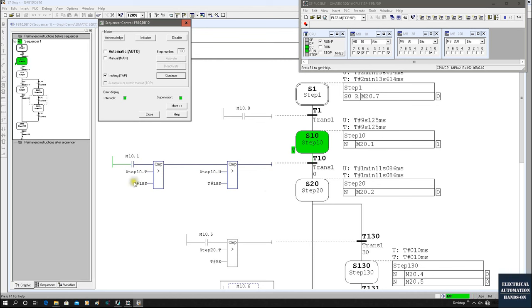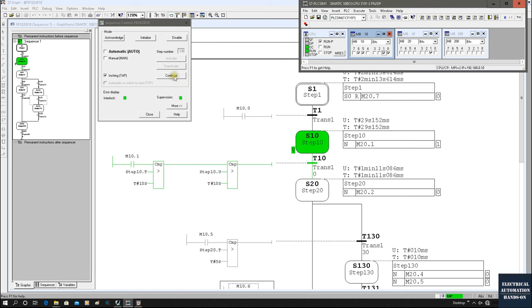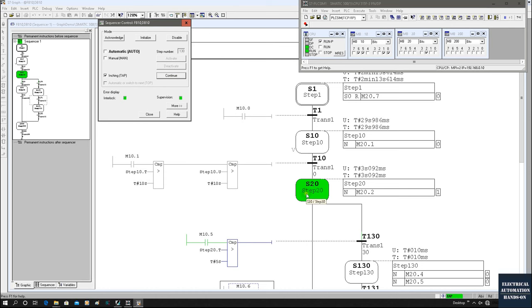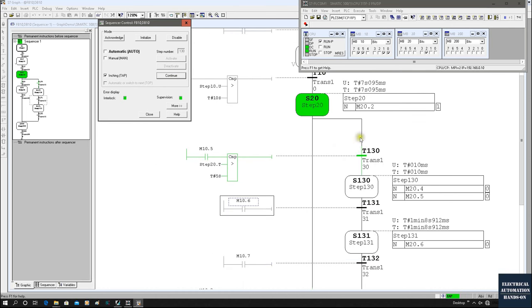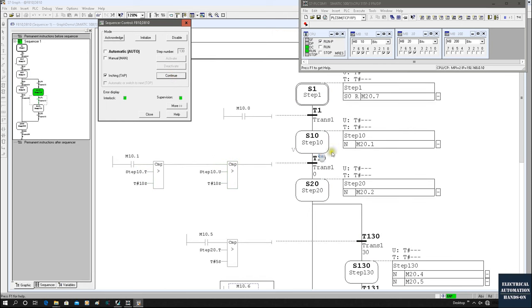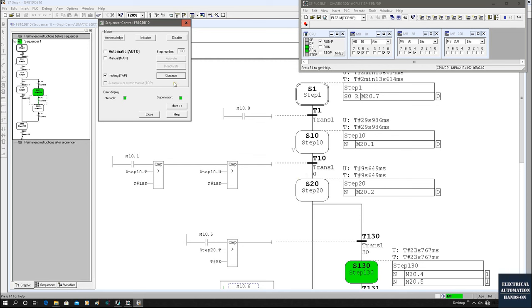Once I click Continue, it jumps to the next step and then waits for a timer or some conditions — for example 10 seconds. Even if I turn on M10.1, the step will still hold because it's waiting for me to click the next step. This is very useful: it's waiting for us to confirm each step before jumping to the next. This step-by-step control is great at the early stages while testing your program to make sure every step is solid and safe before proceeding.